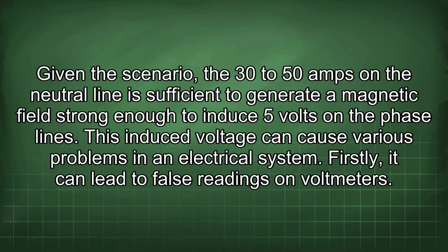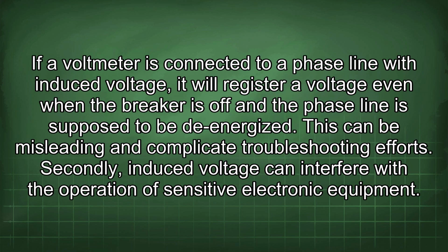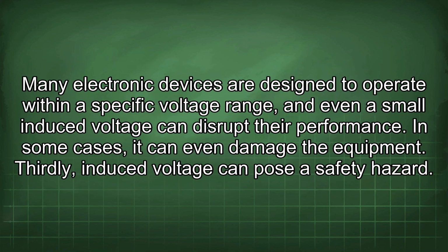Firstly, it can lead to false readings on voltmeters. If a voltmeter is connected to a phase line with induced voltage, it will register a voltage even when the breaker is off and the phase line is supposed to be de-energized. This can be misleading and complicate troubleshooting efforts. Secondly, induced voltage can interfere with the operation of sensitive electronic equipment. Many electronic devices are designed to operate within a specific voltage range, and even a small induced voltage can disrupt their performance. In some cases, it can even damage the equipment.